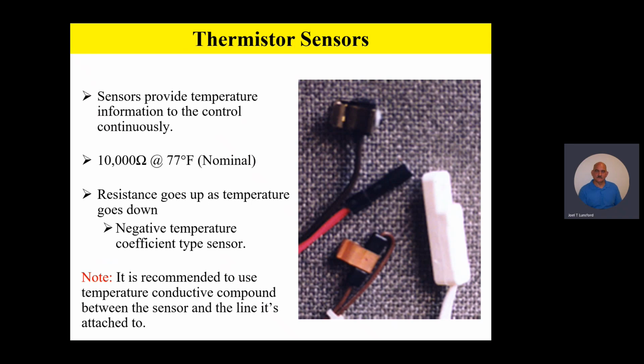And during the heating season, when the outdoor air temperature gets to a certain point and the coil temperature gets to a certain point, it'll force a defrost on the control board. However, year round, it should be noted the sensors are active as long as the defrost control board has 24 volts to it. Now, each one of these sensors is going to have a nominal calibration point of 10,000 ohms at 77 degrees Fahrenheit.